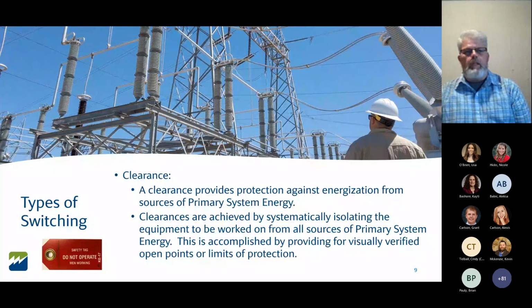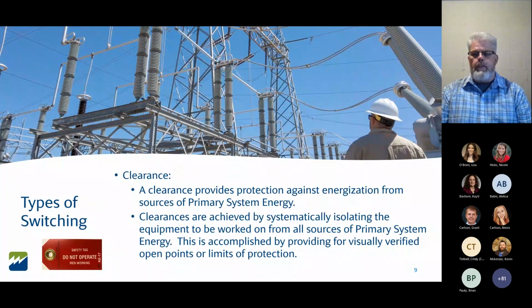The first type of switching we want to talk about is a clearance. This is a big part of our switching—establishing clearances so we can work on equipment. A clearance provides protection against energization from sources of our primary system energy. That's something you'll hear throughout PSOM Chapter 1, our book on how we switch at WAPA, which we train on annually and live by for safe operations of the electrical system. Clearances are achieved by systematically isolating all equipment to be worked on from all sources of primary system energy—electrical energy above 600 volts—accomplished by providing a visually verified open point, or a limit of protection.